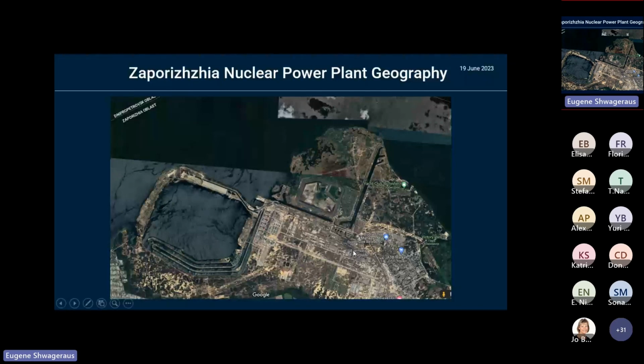Just like any other heat engine, the thermal plant also requires cooling. What we see here around this coast is the water reservoir, with these channels being the intake of water to cool the condensers of the thermal plant. This is a pretty wide channel, which goes all the way to feed the cooling pond, which is itself a complicated structure, but that's our main point of concern. So the feed into that pond goes from the reservoir through the thermal plant, through this channel, and into the cooling pond of the nuclear plant.